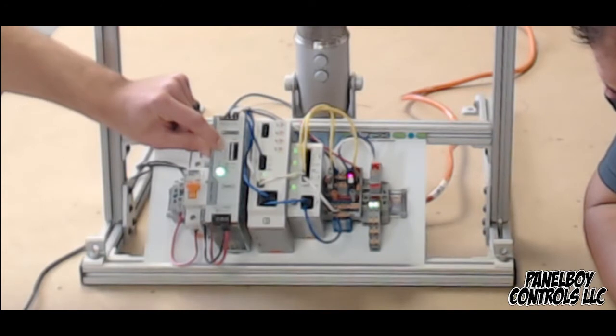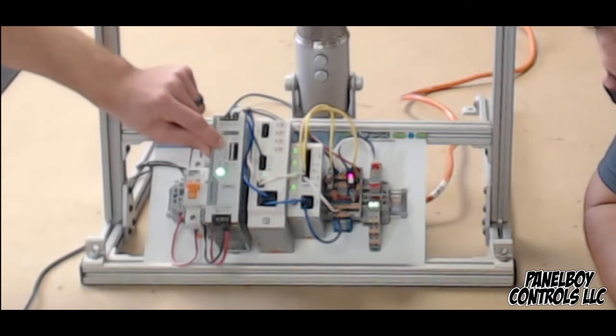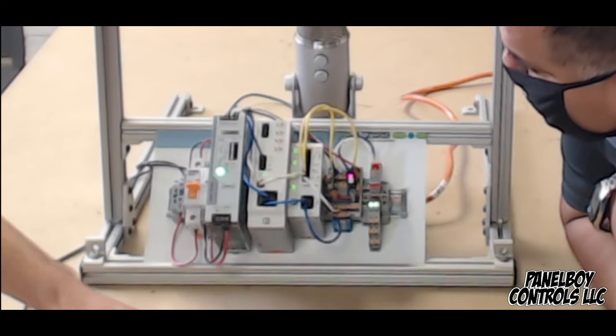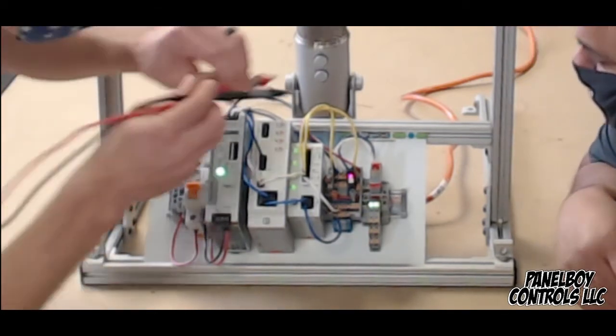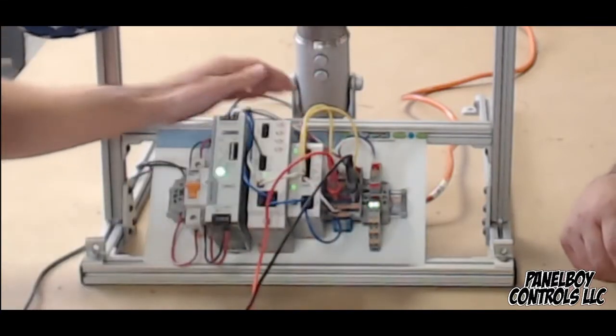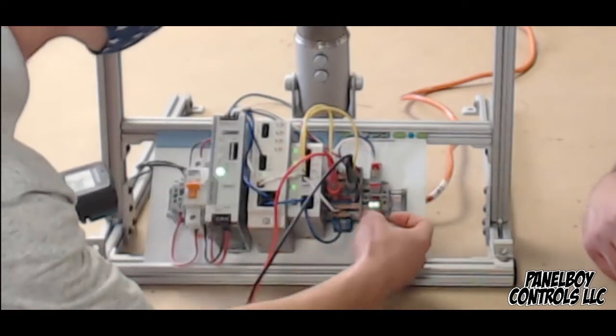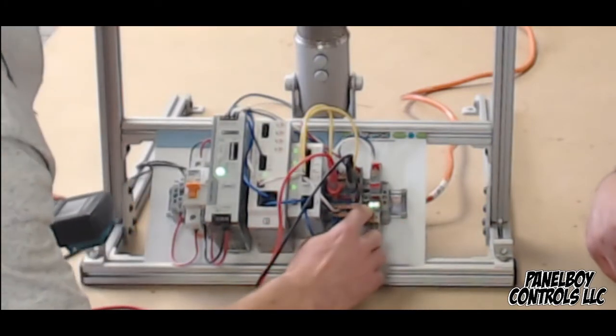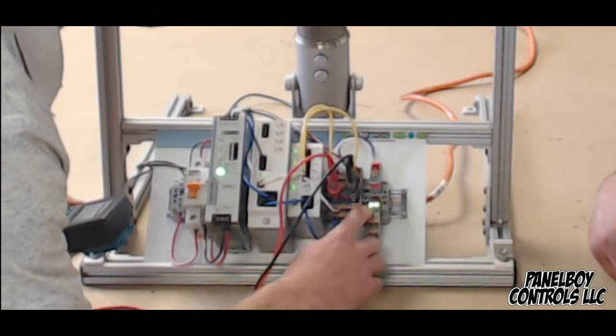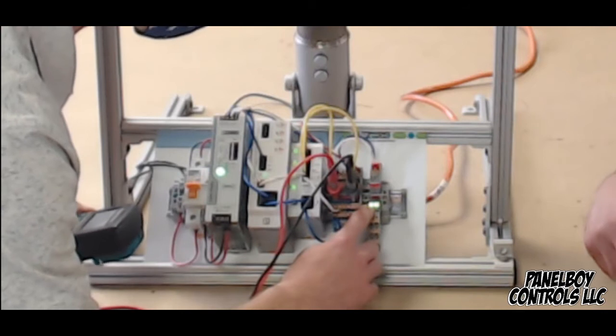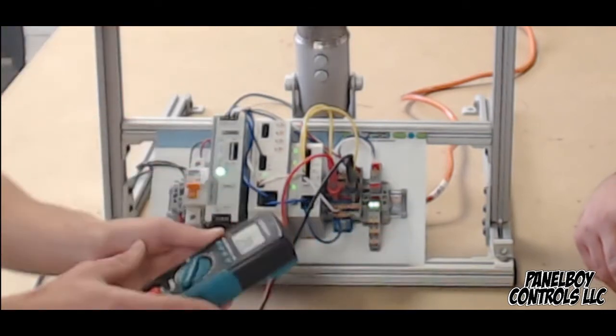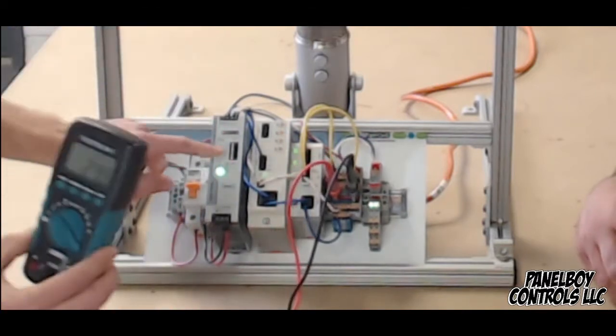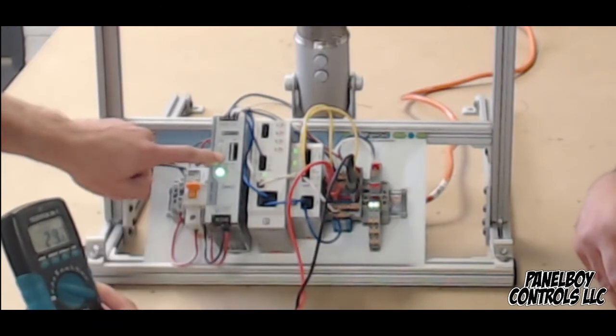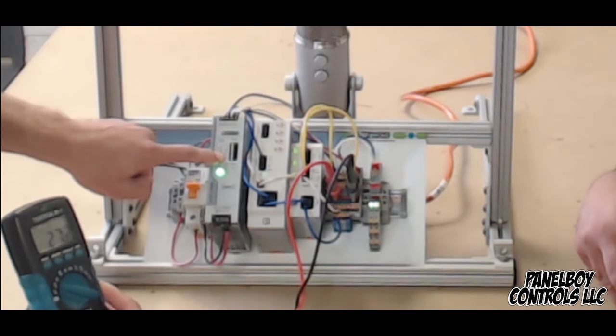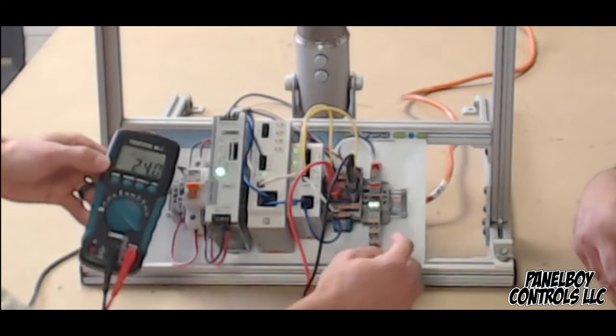Give me a second, I think I'm pressing the button. So right now you're increasing it? Yeah, we're going to do this the right way. Just like the other ones, if I want to set this, I press and hold, and after a few seconds it'll let me reset it. You'll see right now it's set at 29.5 volts. It might not be letting me reset it because I'm holding the button down. Let me drop the voltage to 24 volts, and now I'm going to reset it.